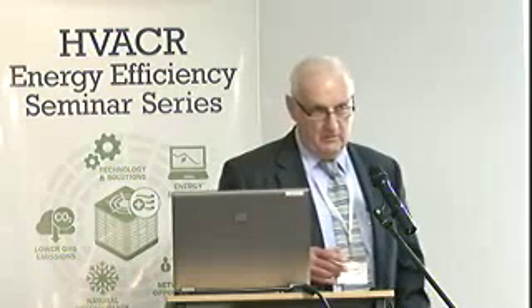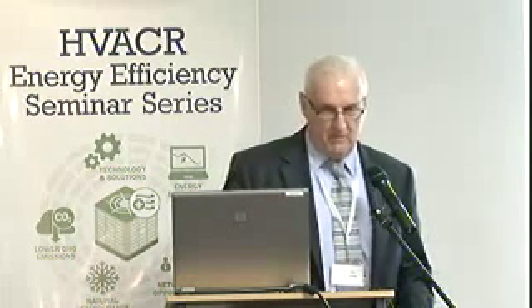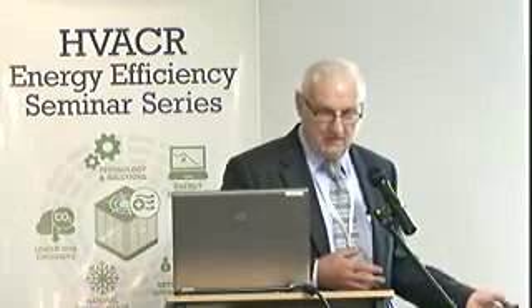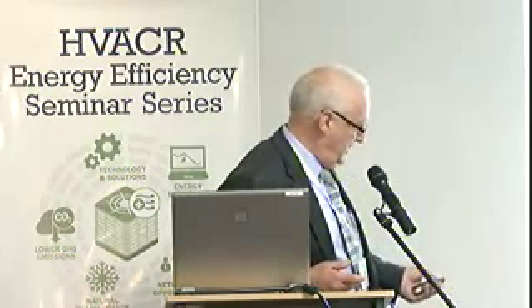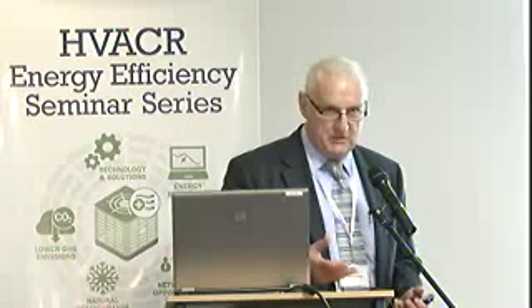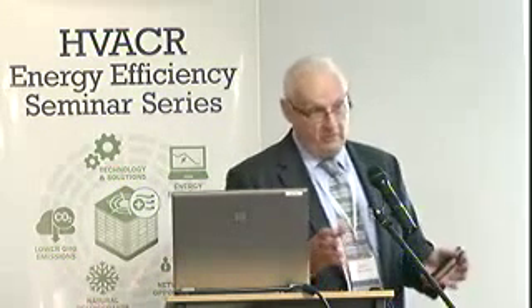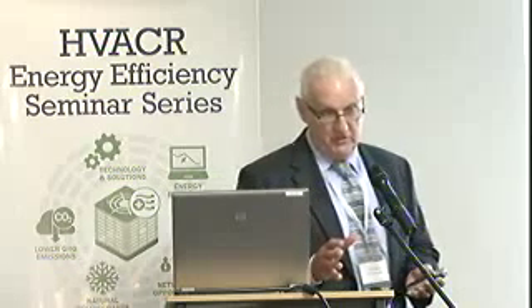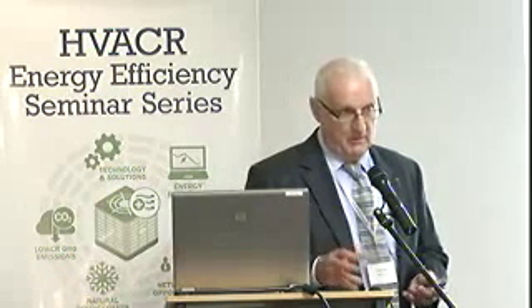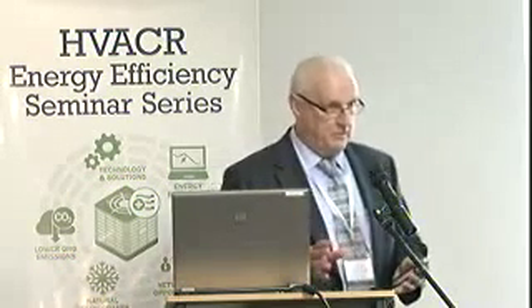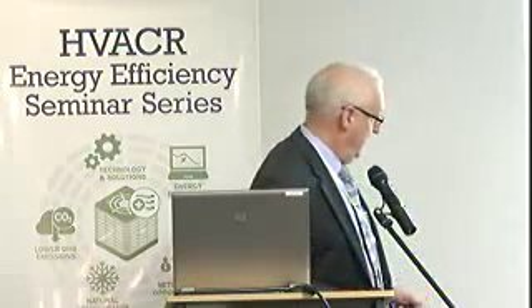But it is something we've got to watch for, because sometimes motors can be at a higher level. And we'll see some performance graphs in a moment about why we're cautious about that. Knowing this helps us in our prediction of what the energy savings are, and in some instances, whether in fact we should be doing voltage optimization for that particular motor. That's quite a rare occurrence where you wouldn't, because mostly they're 380 to 415 volt motors.